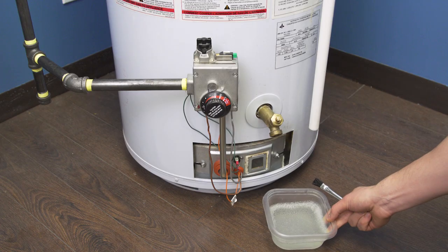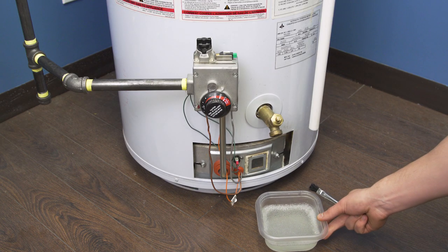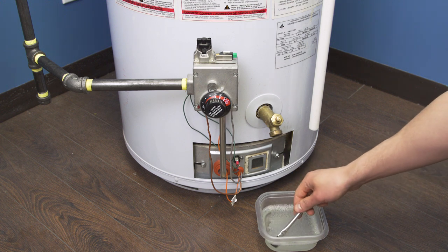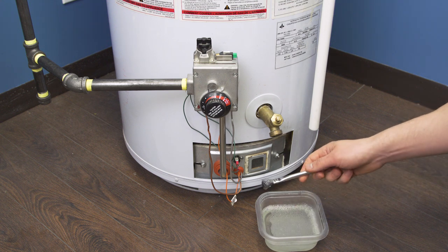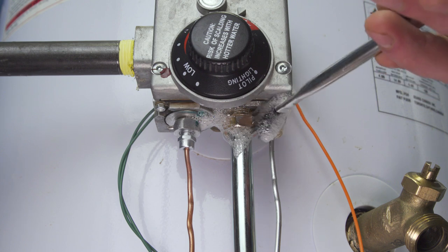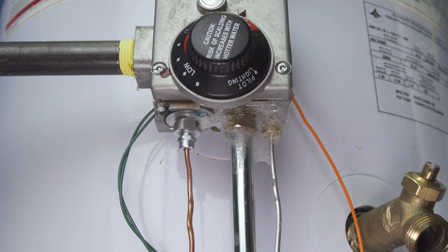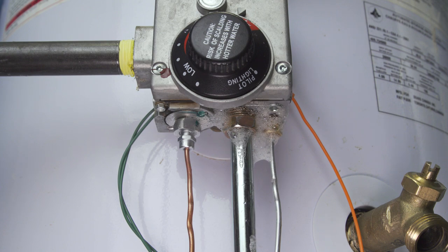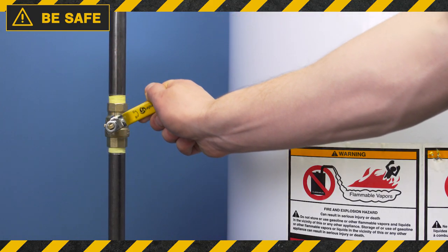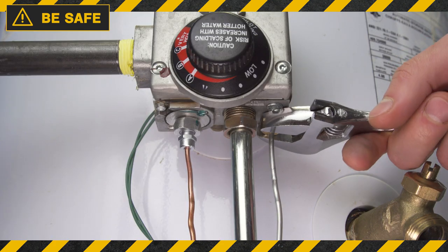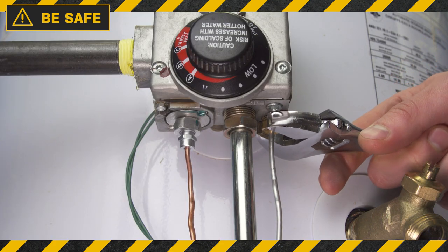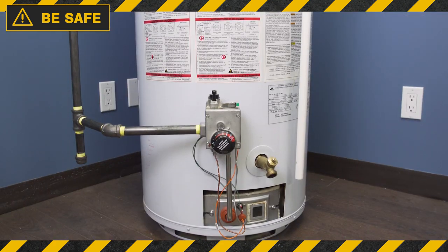While the burner is running it's best to do a final test to see if any gas is leaking. Apply a soap solution to the pilot and manifold tube connections. If you see any bubbles growing or if you smell a strong gas odor then turn off the gas and check your connections. If the problem persists then call a technician.